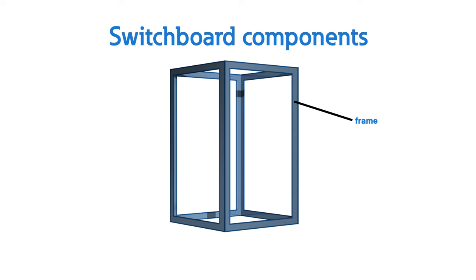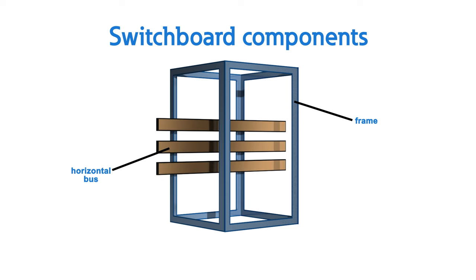The switchboard frame is the metal skeleton that houses all of the other components. The bus, which is either copper or aluminum, is mounted within this frame. The bus distributes power from the incoming cable conductors to the branch circuit devices. A horizontal bus distributes power to each switchboard section, with the standard orientation being ABC from top to bottom.